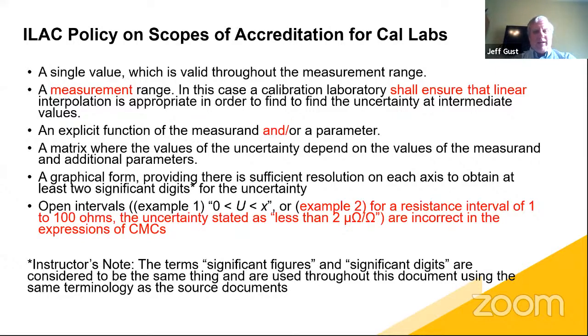And again, we clarified that open intervals, for example, saying that on a range of 0 to 1,000 volts, my uncertainty is better than or less than 2 parts in 10 to the 6, is an incorrect expression of the CMC. You just can't say, well, I'm better than this, but I may report smaller. You just can't do that. So that's a pretty important aspect that we had to kill off, because that did nothing but invite ambiguity into the process as well.